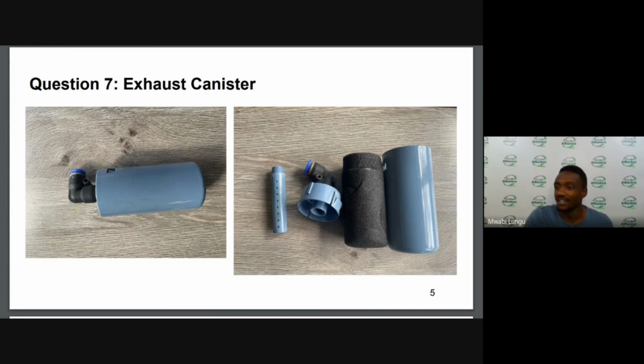All right, so the next question says, we have an OxyPure oxygen machine at our facility that works well when being used at 3 to 5 liters per minute, but alarms and gives a low flow error when it is run at 1 to 2 liters per minute. What can be the cause of this?